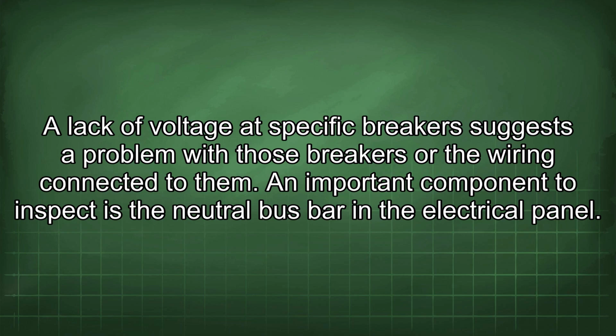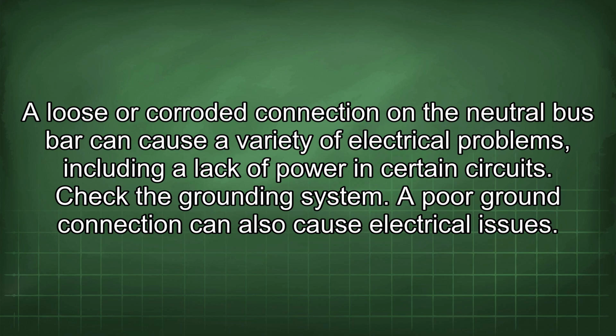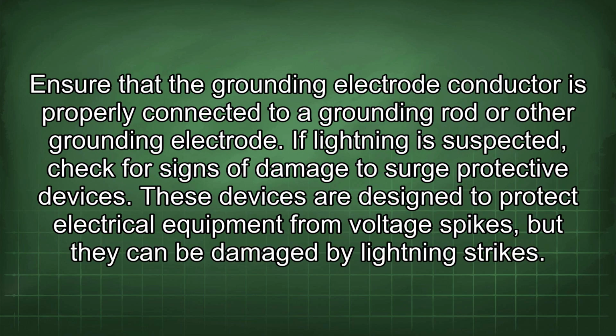An important component to inspect is the neutral bus bar in the electrical panel. A loose or corroded connection on the neutral bus bar can cause a variety of electrical problems, including a lack of power in certain circuits. Check the grounding system. A poor ground connection can also cause electrical issues. Ensure that the grounding electrode conductor is properly connected to a grounding rod or other grounding electrode.